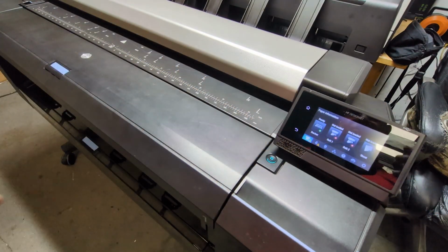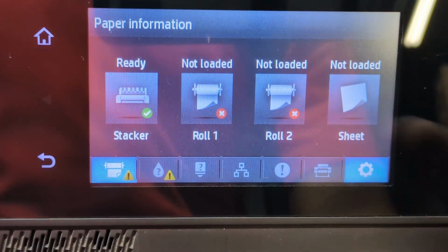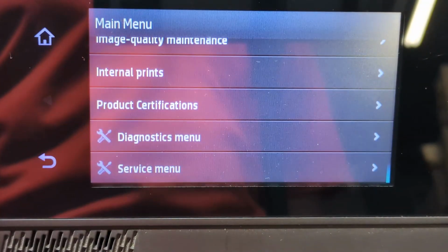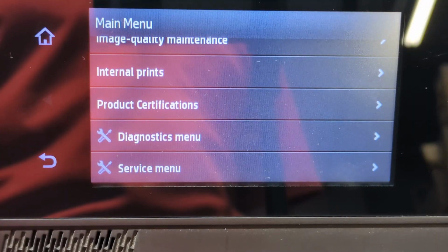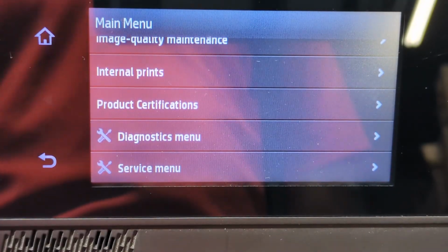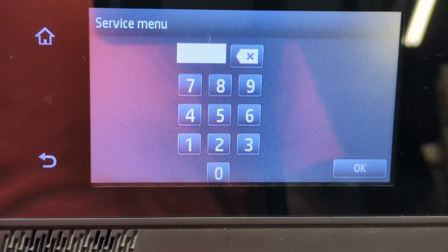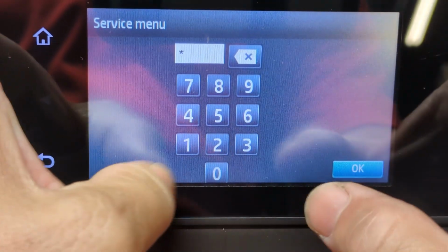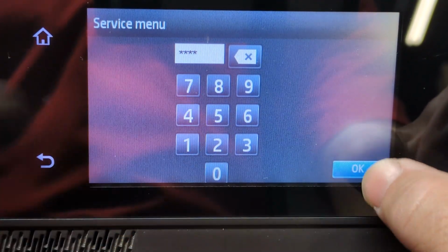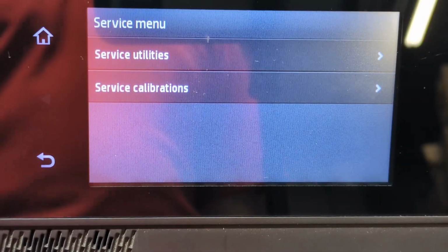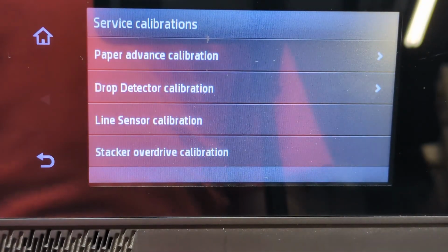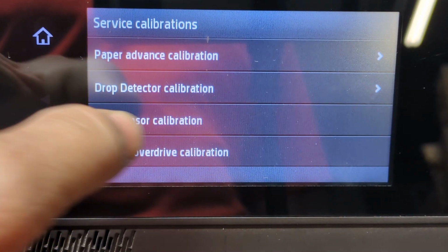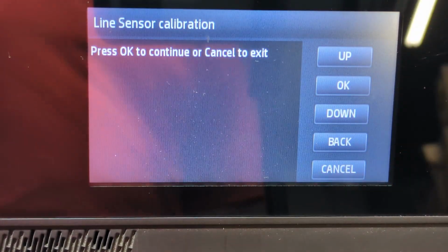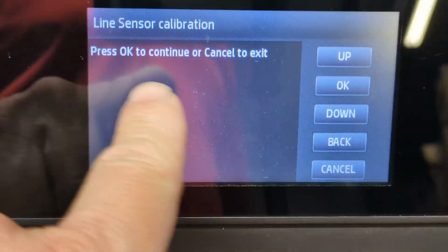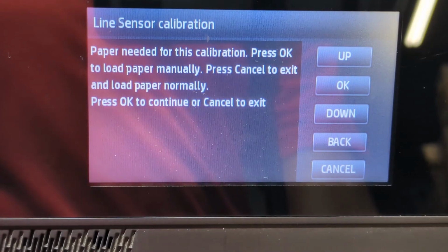Let's head to the menu. Okay, so at the menu, you're just going to hit the settings tab, scroll all the way down to service menu. And then the code is 3174. And go ahead and press OK. And then service calibrations at the bottom. And then you're going to see line sensor calibration. Now it's going to tell you to press OK to continue or cancel. We're going to press OK.